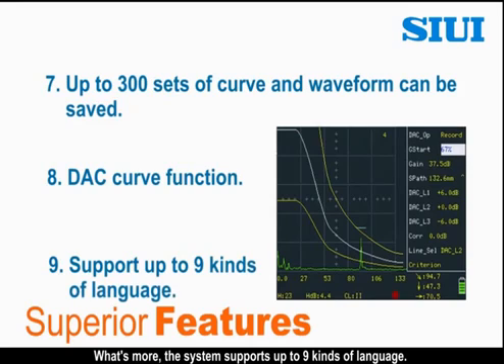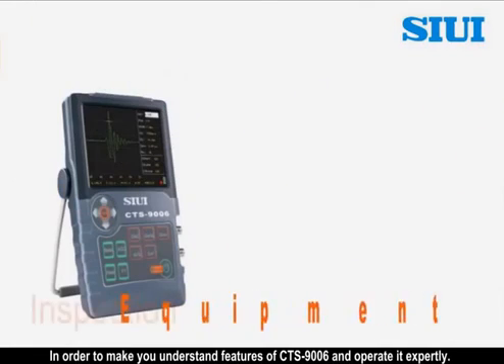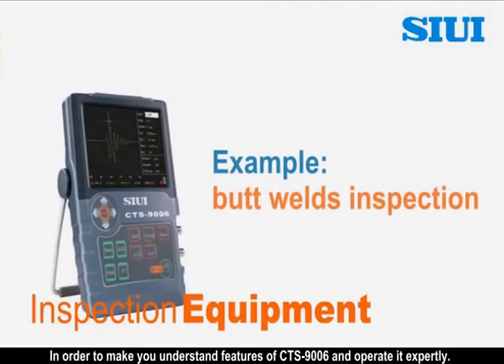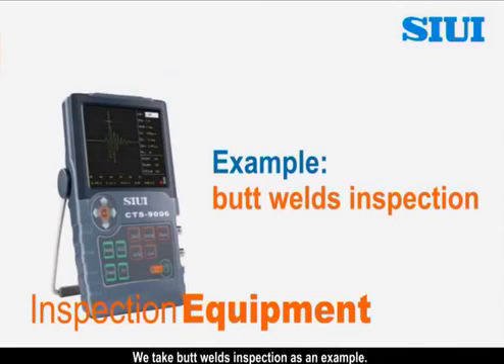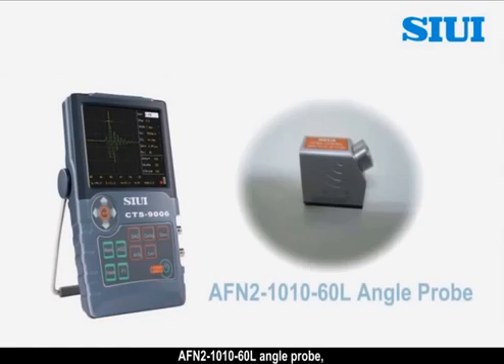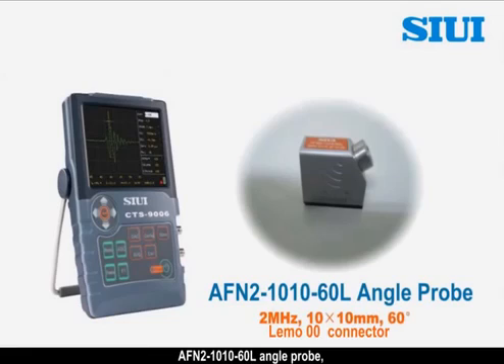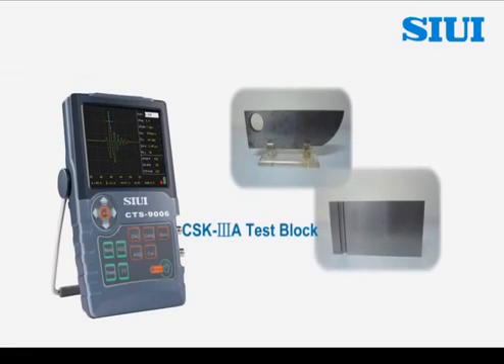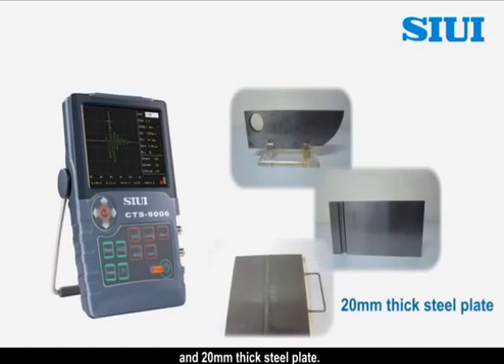What's more, the system supports up to 9 kinds of language. In order to help you understand the features of CTS-9006 and operate it expertly, we take butt weld inspection as an example. In this inspection, we use CTS-9006, AFN2-1010-60L angle probe, V1 test block, CSK-3A test block, and a 20mm thick steel plate.